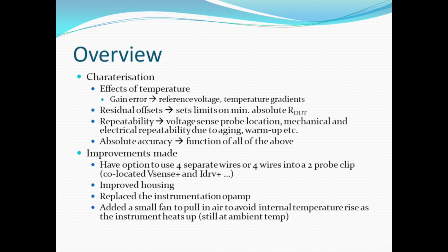So the first important thing I noticed was the effects of temperature, and that is basically results in gain errors, and mostly has to do with the reference voltage change and also the change in the resistance of the main current setting resistor, which I will show later. There are also residual offsets from the input offset of the instrumentation amplifier plus the offset of the offset compensation loop itself, and so I will go into that a little bit.